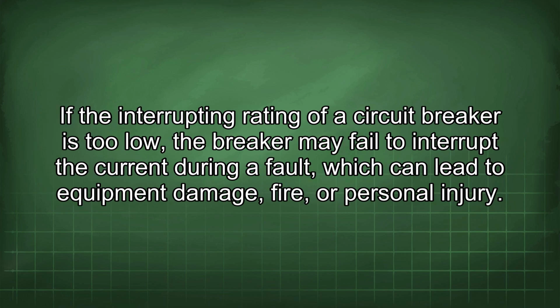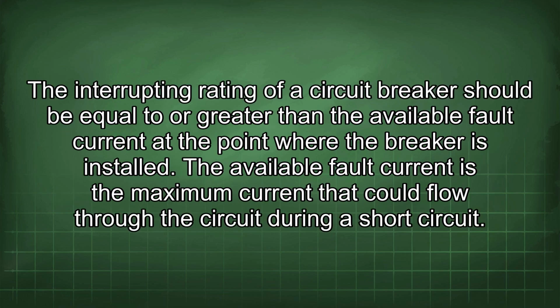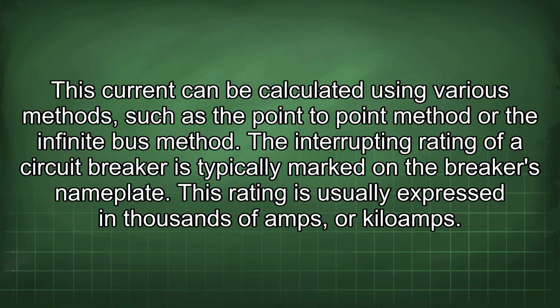If the interrupting rating of a circuit breaker is too low, the breaker may fail to interrupt the current during a fault, which can lead to equipment damage, fire, or personal injury. The interrupting rating of a circuit breaker should be equal to or greater than the available fault current at the point where the breaker is installed. The available fault current is the maximum current that could flow through the circuit during a short circuit. This current can be calculated using various methods, such as the point-to-point method or the infinite bus method.